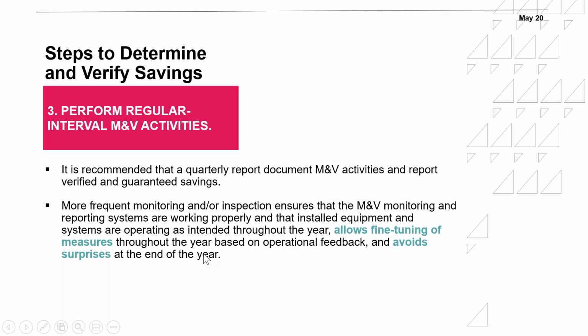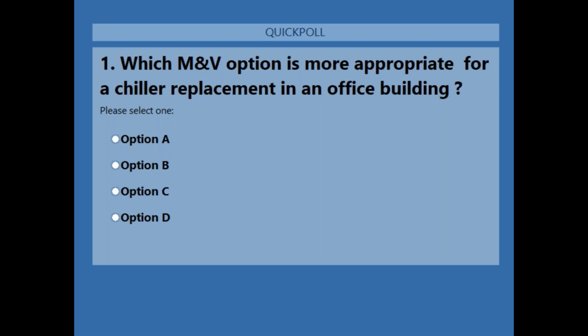Now, I have some polls here that I'm going to start sharing. We discussed the different options, A, B, C, and D. I'm going to launch the poll now. The question is, which M&V option is more appropriate if you want to change one chiller in a building, just one chiller? Should you go with option A, B, C, or D? Remember, with a chiller, a lot of parameters need to be captured. It's not as easy as lighting. You probably will need to check the kilowatt per ton, the temperatures, delta T, outdoor temperatures. If it is water cooled, maybe the wet bulb. If it's air cooled, the dry bulb. And remember, it's only one chiller.